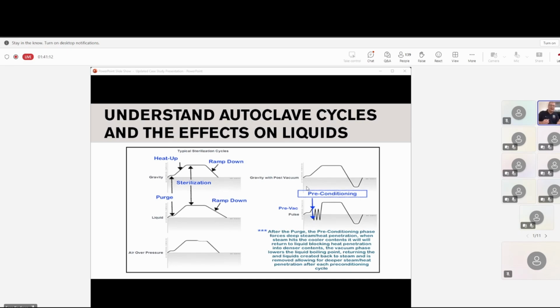If you lose more than 10% and you start losing 20-30% and you see media splattering, you either need to change your settings to slow the ramp down a little bit more, or you have a leak in the chamber or a bad steam trap, and you need to call your technician, and then they can make that adjustment. Over here for the preconditioning. Now this, where the gravity in the liquid was the tack hammer, this is the jackhammer. This is what this preconditioning does, and pre-vac or preconditioning. And you see how aggressive those lines are.